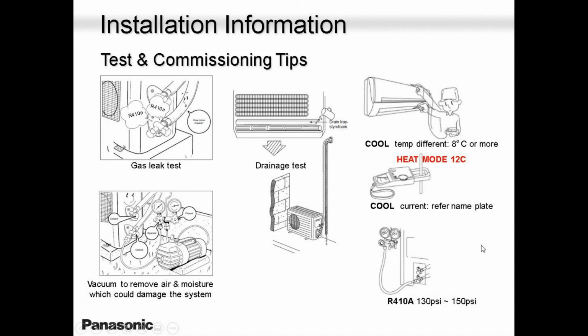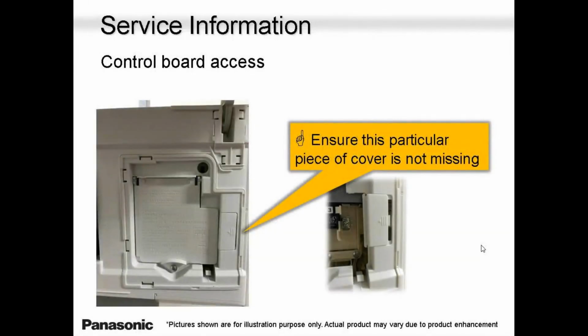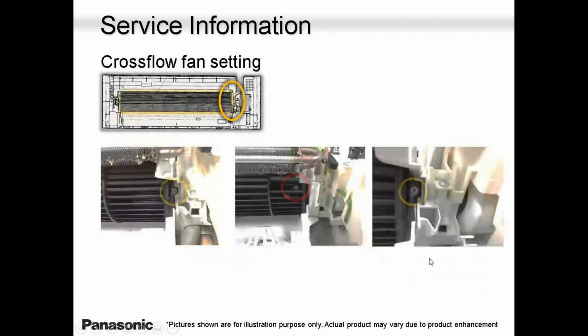After installing your system, if you're running it in cooling, always remember the temperature difference between intake and discharge. Always try and keep it around 7, 8, 9 degrees. You're good. And 12 degrees in heating. It all depends on the area. Meaning, if the fan speed is too high, you might get a bigger delta T. If the fan speed is at medium, you will be okay. So please try and get these values to make sure that the system is working the way it's supposed to.